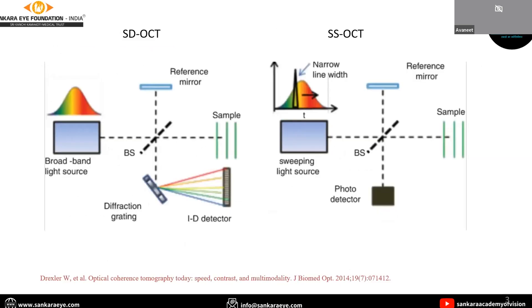That was time domain OCT. In spectral domain OCT, the point detector is replaced by a spectrometer, and there is no need for mechanical scanning of the optical path length. In swept source OCT, the broad bandwidth light is replaced by a narrow linewidth source which sweeps over different wavelengths.